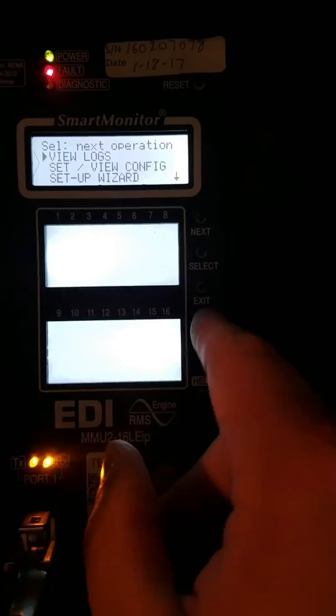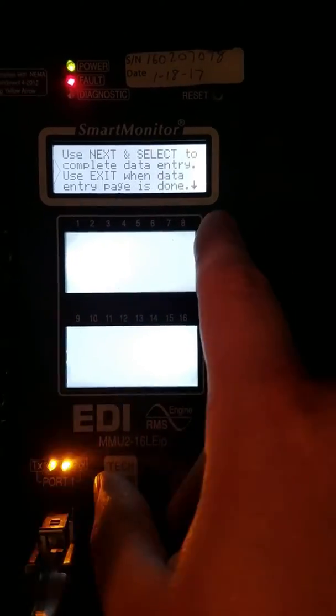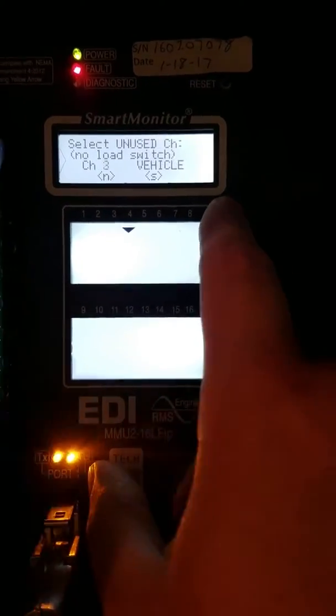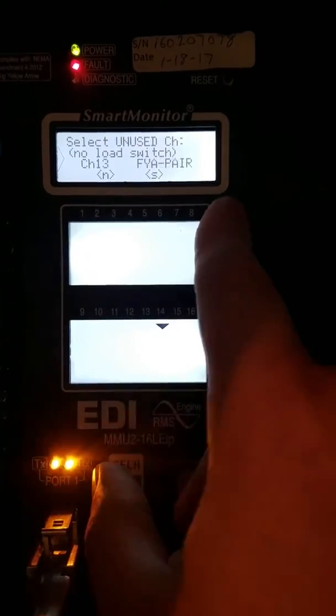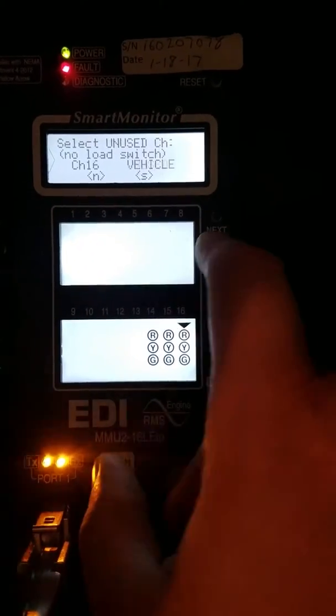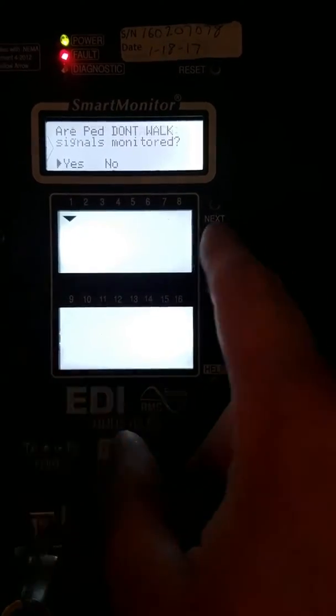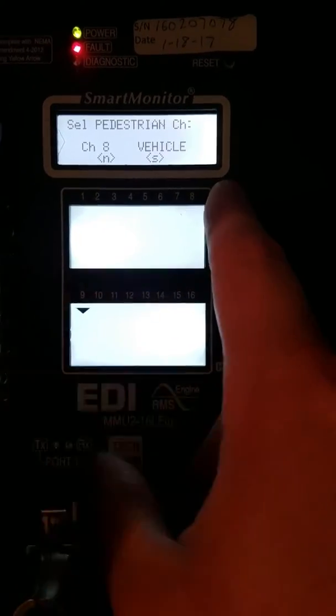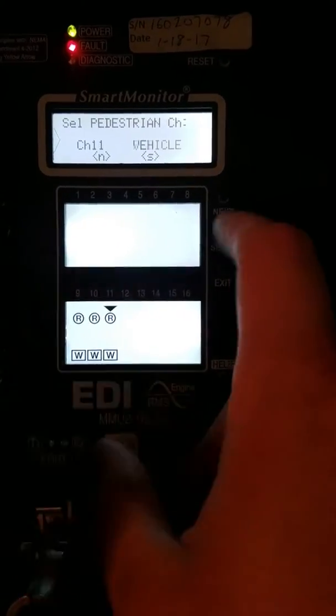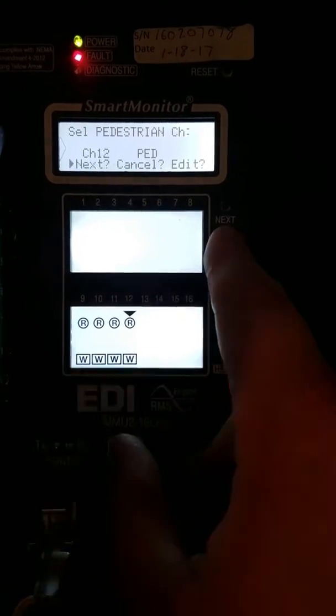Now we're going to exit again and then go to Setup Wizard. We're going to select the channels that don't have any load switches in them. In this case, the last three here, because we have PEDs. PED channels are 9, 10, 11, 12. We hit Exit, Select.